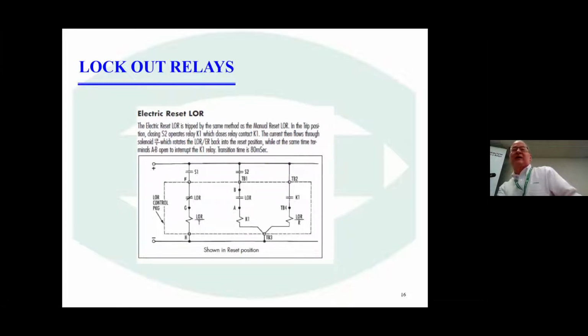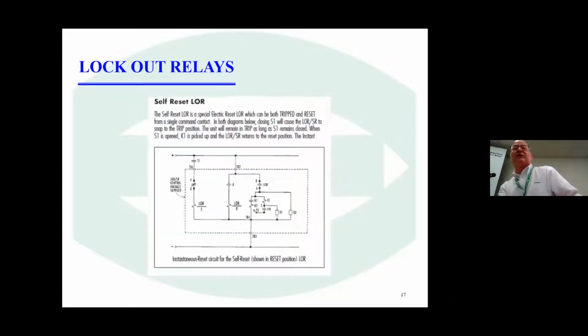In an electric reset lockout relay, I've got two system protection contacts, an S1 and an S2, where S1 activates the lockout relay and S2 resets the lockout relay. And that's what I demonstrated before in my tabletop. The third version is the self-reset lockout relay, and that only requires a single system protection input contact. So when it's closed, it operates, and when it's opened, it resets. I do have one of those devices here, so I'm going to go back and do my favorite thing, which is to share and demonstrate.